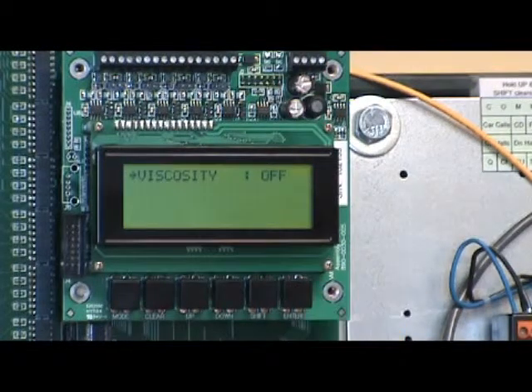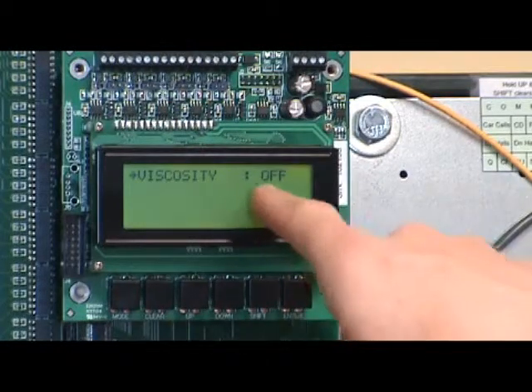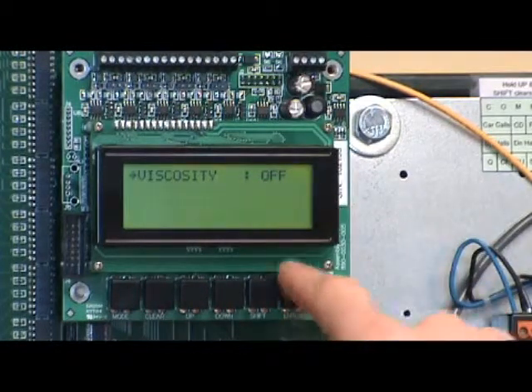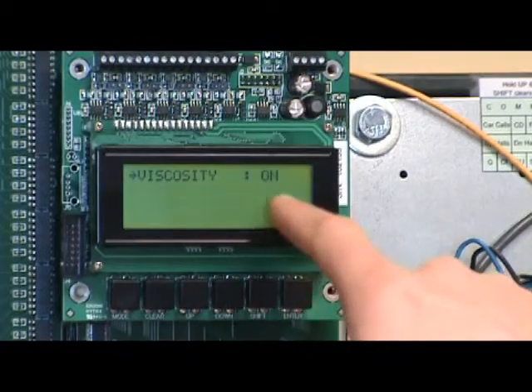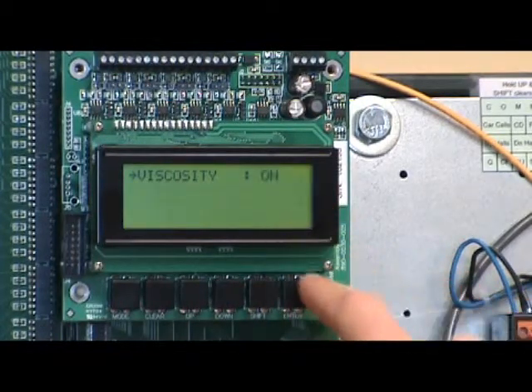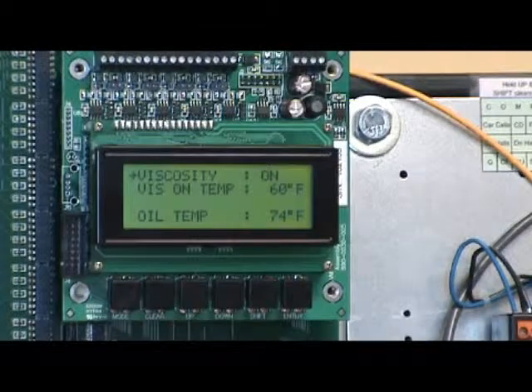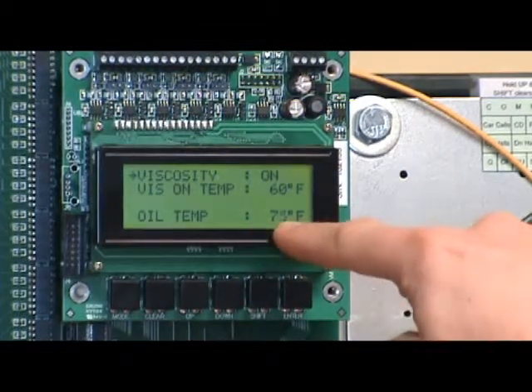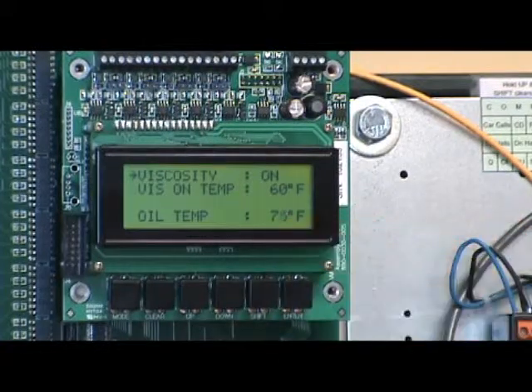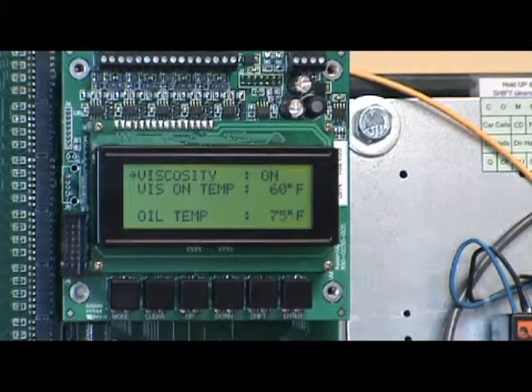Once we hit enter, they're always actually in the parameter list. They're not turned on. I shouldn't say on. We're going to see that this one is turned off. We're going to hit enter, use the up arrow or down until it's flashing on, and hit enter. Now that's going to reveal what the actual temperature sensor reading is down at the bottom here. It's saying 74, 75 degrees. It's very accurate. It's going to tell you within 1 degree what the actual temperature of the oil is.